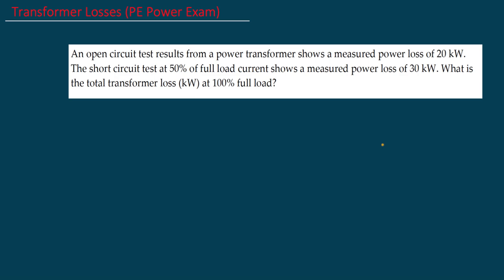We have the open circuit test result and the short circuit test result at 50% full load. The total losses at 100% load equals the I²R losses at 100% plus the no-load losses.